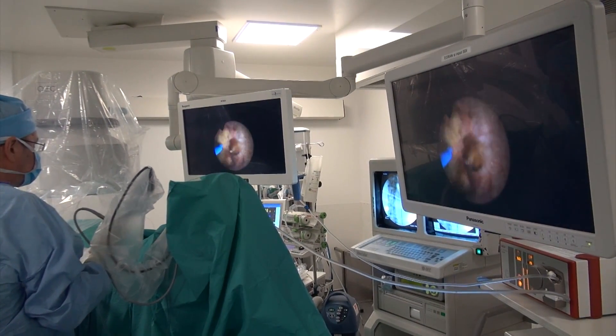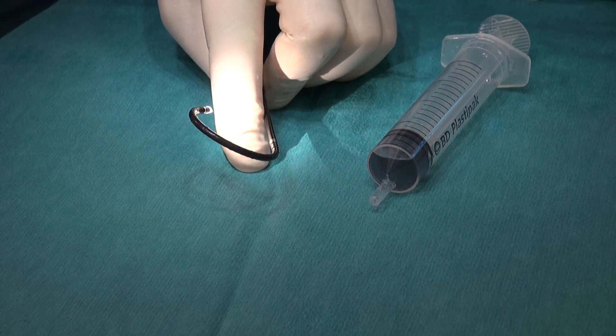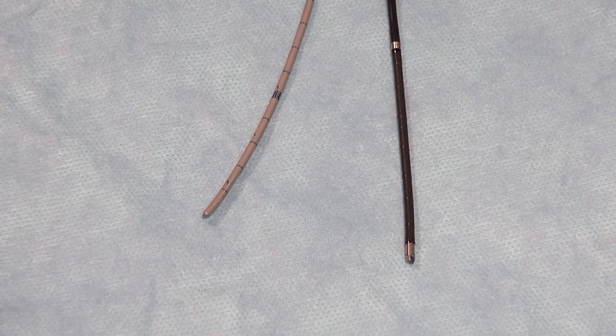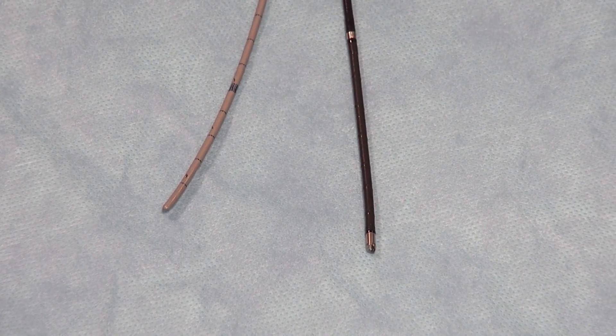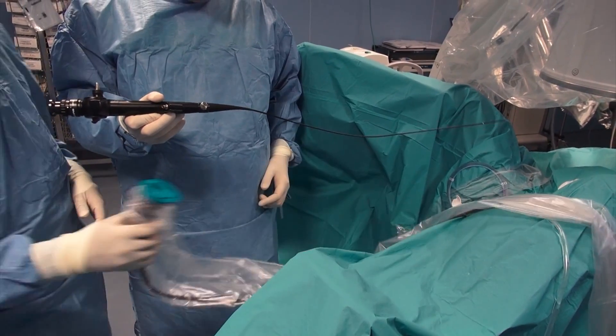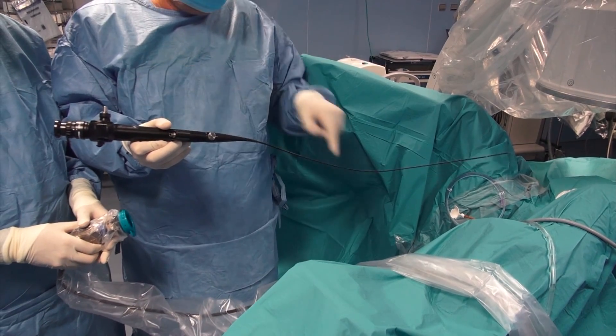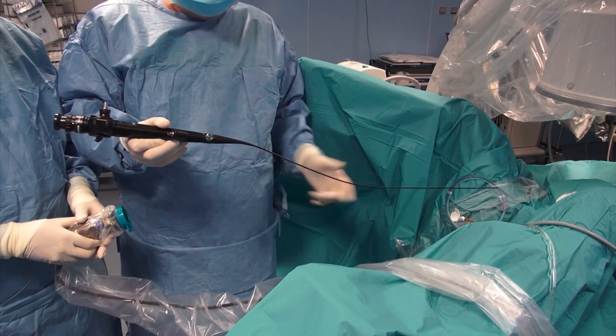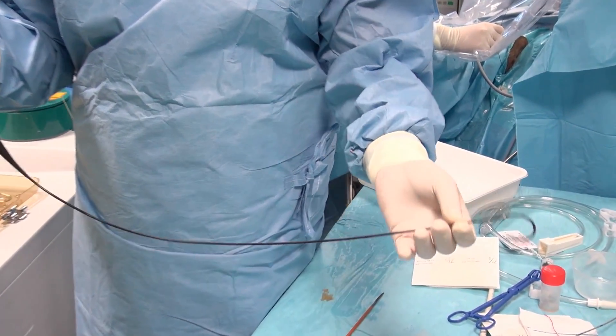More recently, a smaller fiber-optic ureteroscope has become available: the URF P6. It has less than 8 French shaft diameter, comparable to the caliber of a standard ureteric catheter. The stiffness of this instrument allows easier introduction and progression inside the ureter. Flexion and deflection is of 270 degrees.